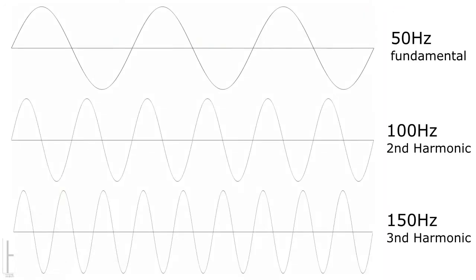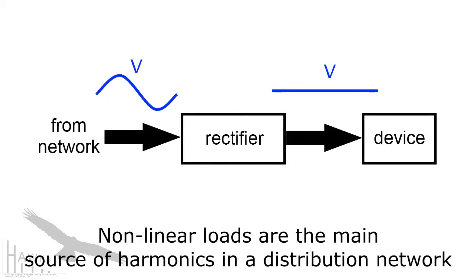Harmonics refer to any additional signal that has a frequency that is an integer multiple of the fundamental frequency. In a distribution network, current harmonics are drawn by nonlinear loads, devices that convert the voltage signal into another form, through a rectifier, ADC, or some other form of power electronics.